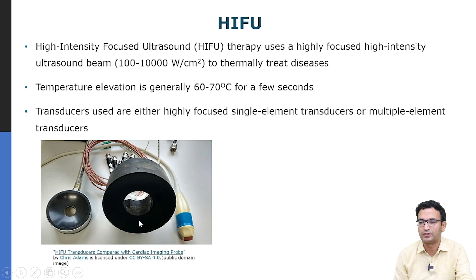You can see these transducers are very large in size compared to a traditional ultrasound imaging array, and these transducers are able to generate a sharply focused beam which can have high intensities. Just by exposing for a few seconds, these transducers can actually enhance the temperature of the tissue by 60 to 70 degrees, and because of that the tissue undergoes thermal necrosis and is destroyed. So, effectively it is like destroying a certain region, just like you would excise a certain tumor. Here, without any scalpel, without cutting open the tissue, you can destroy a certain region from outside, or non-invasively, which is the most interesting aspect of HIFU surgery.